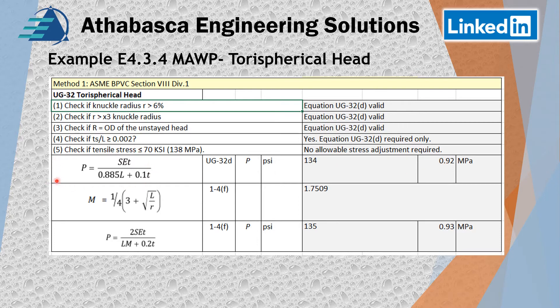Now we do our calculation because we want to find the maximum allowable working pressure. We take UG-32D and work it out, and we calculate our pressure to be 134 PSIG. We also do some additional checks — just for interest, in case we needed to go to Appendix 1-4F, what would happen? We take that equation, it's a geometry setup, and we get 1.7509. We calculate the pressure and get basically the same answer.